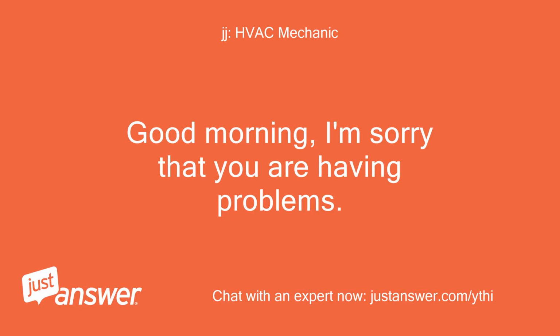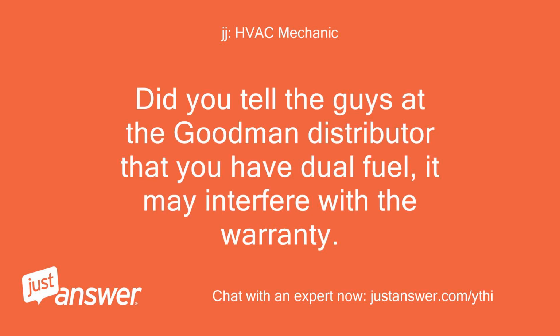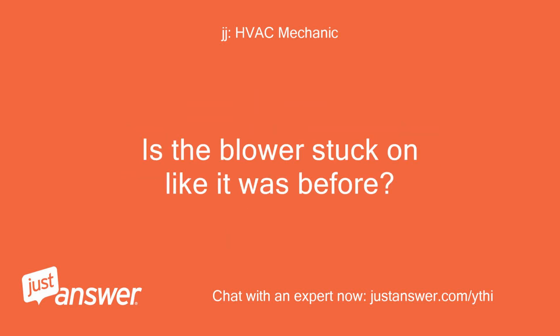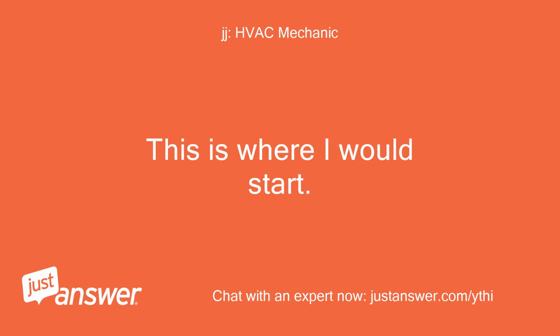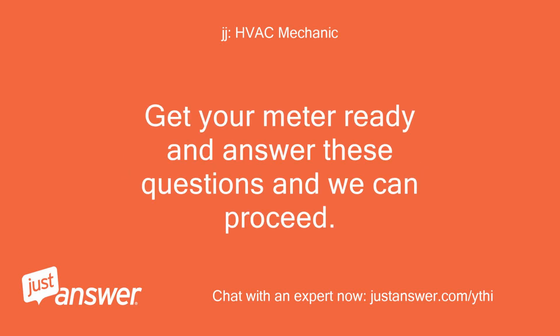Good morning, I'm sorry that you are having problems. Is it possible that the wood-burning system is too hot for the furnace high limits? Did you tell the guys at the Goodman distributor that you have dual fuel? It may interfere with the warranty. Is the blower stuck on like it was before? This is where I would start. I will be here to help you. Get your meter ready and answer these questions and we can proceed.